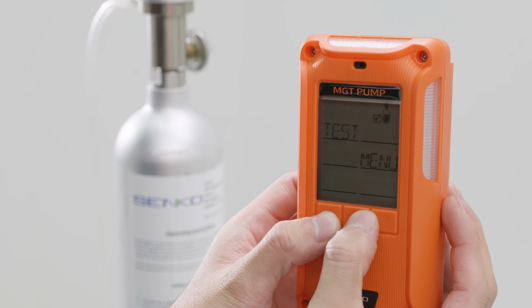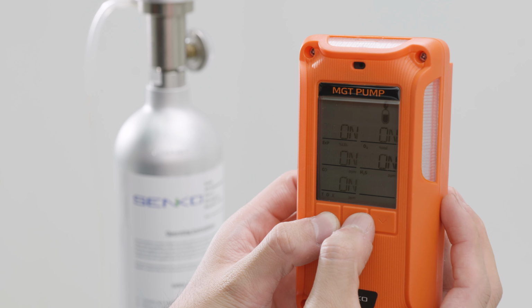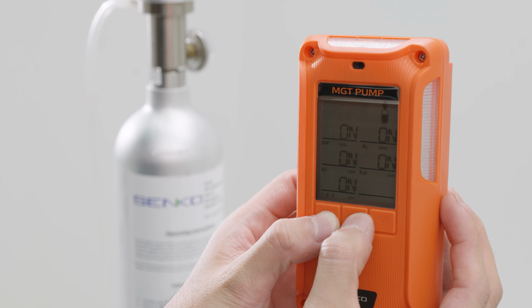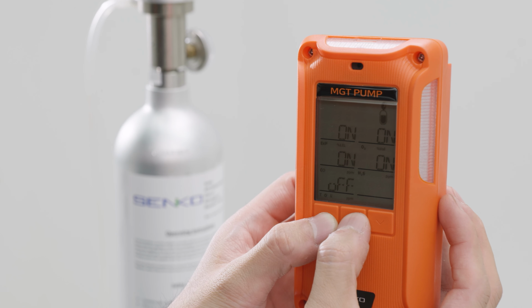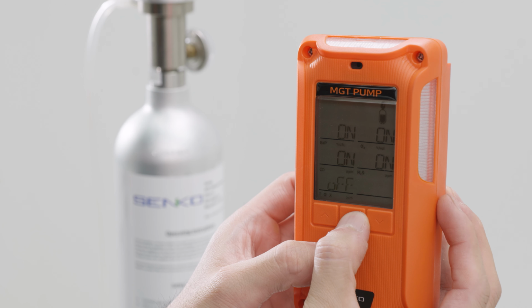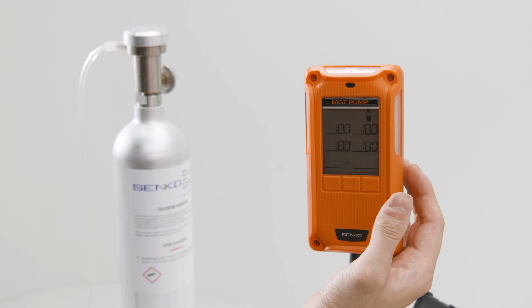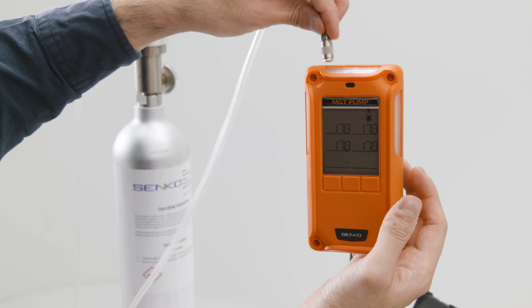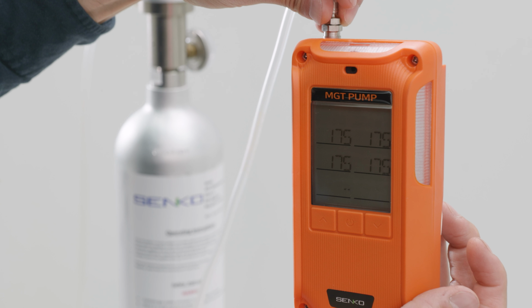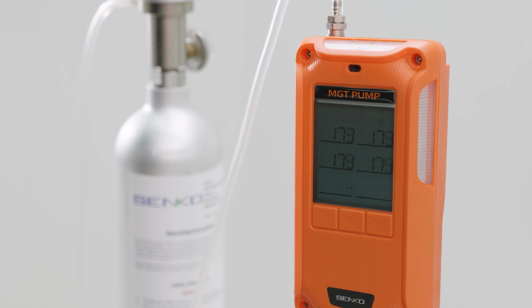The bump test is a test in which test gas at the secondary alarm concentration level is applied to verify that the audible alarm, sensor response, LEDs, and vibration are functioning properly. Although it may appear similar to the self-test, the primary purpose of the bump test is to confirm proper sensor and alarm operation. The execution procedure is the same as performing span calibration, where gas is applied to the device using a calibration gas cylinder during the test.